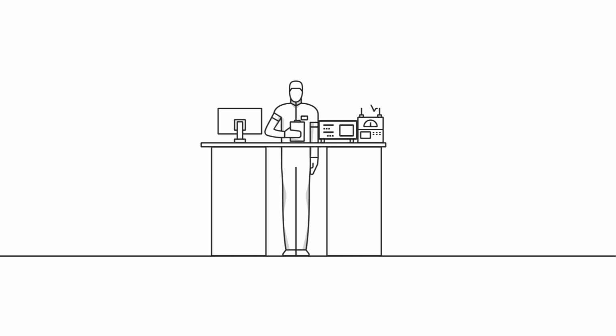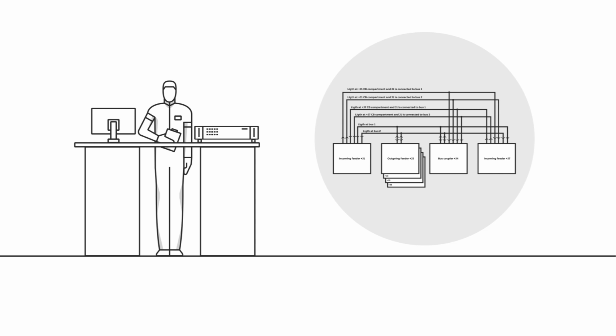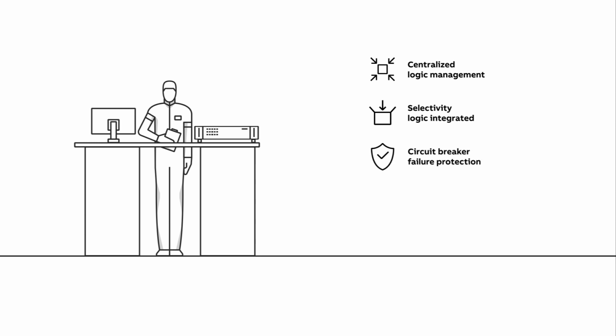If a similar system would be built with SSC600, however, the situation is quite different. With SSC600, there is no need for connections between the protection relays. The SSC600 receives all the current and light information from the protection relays, thus all the logics can be handled in a centralized manner. Further, selectivity logic is integrated into SSC600, which makes engineering faster and the switchgear easier to maintain. SSC600 also offers circuit breaker failure protection, so it is easy to increase arc flash protection reliability. It is also straightforward to add this kind of functionality as the logic is already in the SSC600 device.